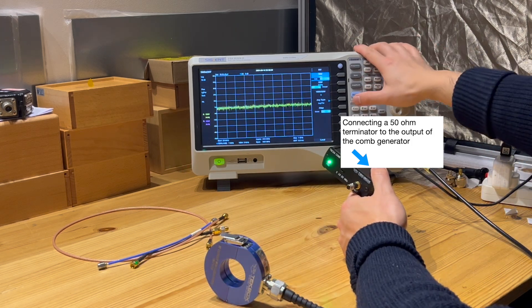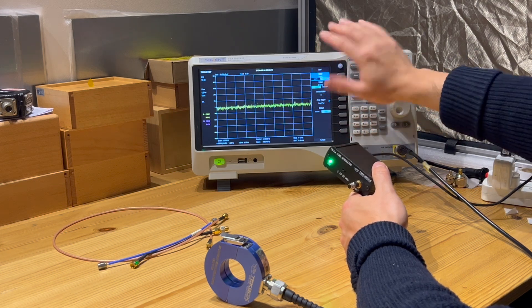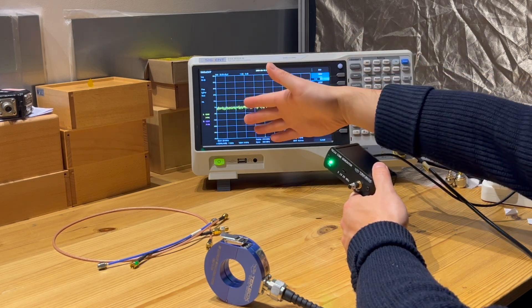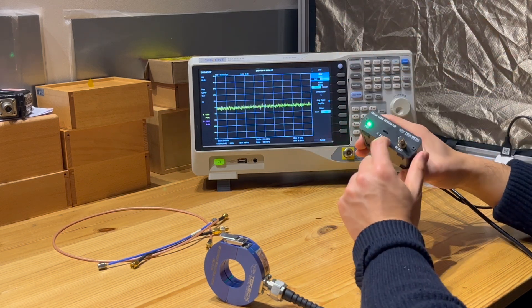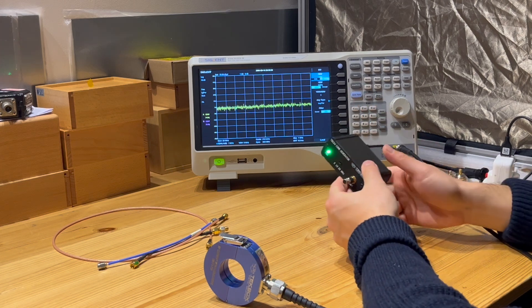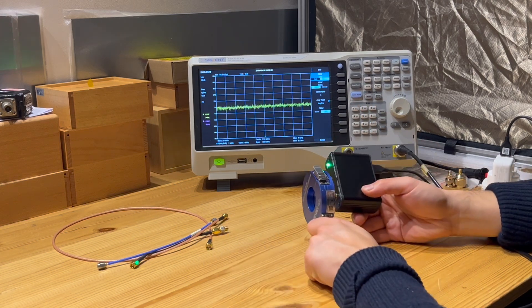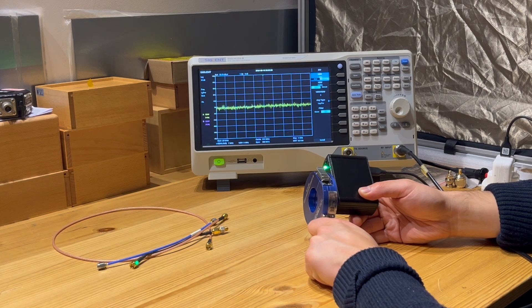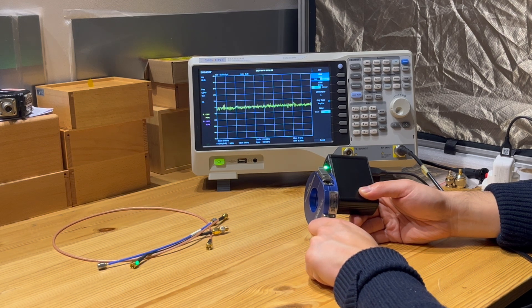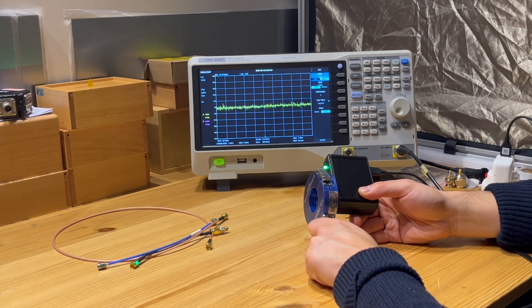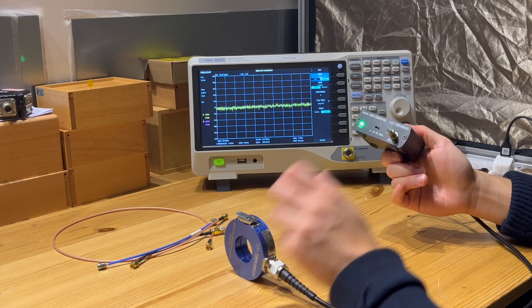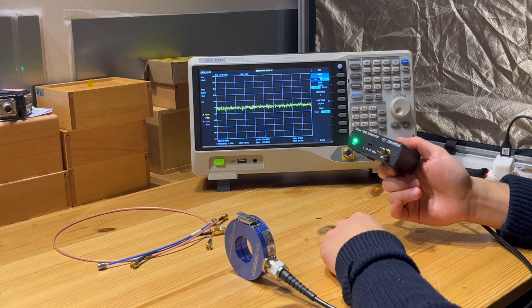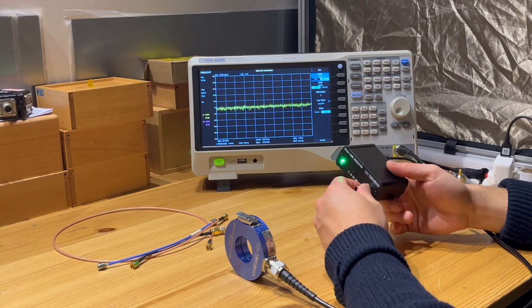In terms of the setup I use a pre-amplifier with no attenuator, starting from 20 megahertz, stop at one gigahertz because I selected 20 megahertz comb frequency. Let's see if there's any leakage coming from here. I put it in here and as you can see, currently I do not measure any leakage noise, which means the comb generator is well shielded at least up to one gigahertz.